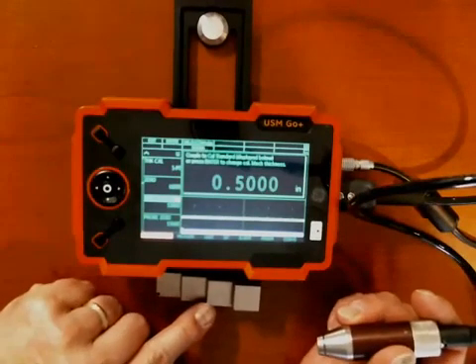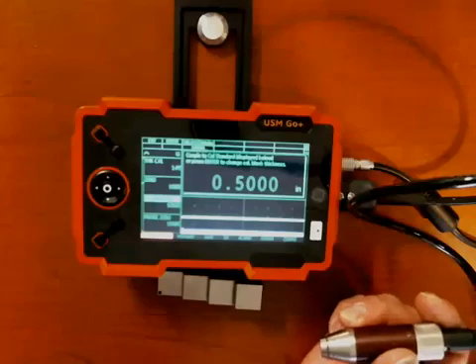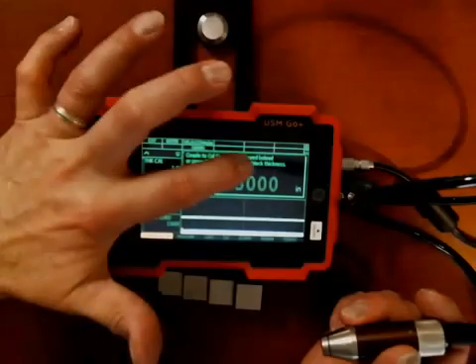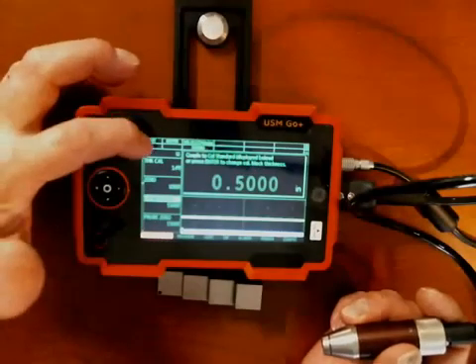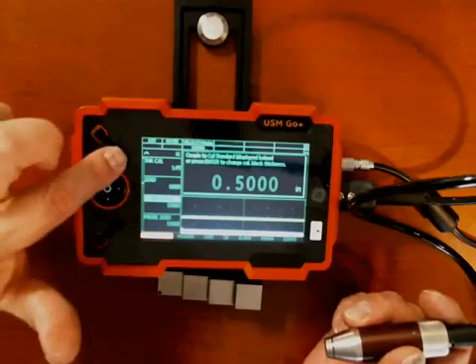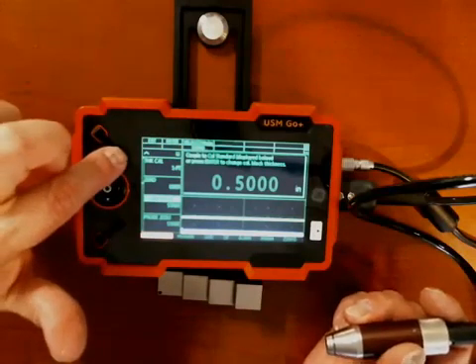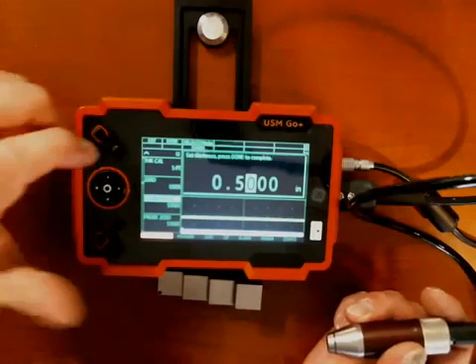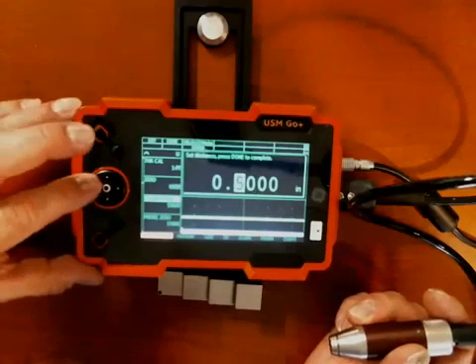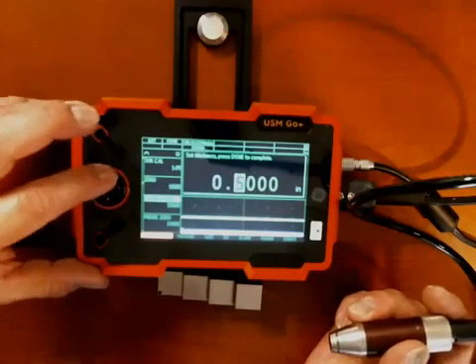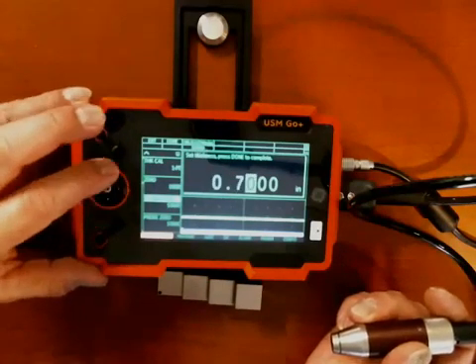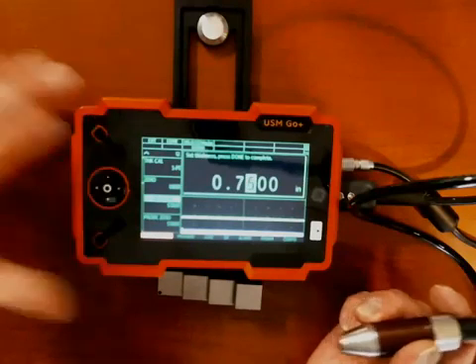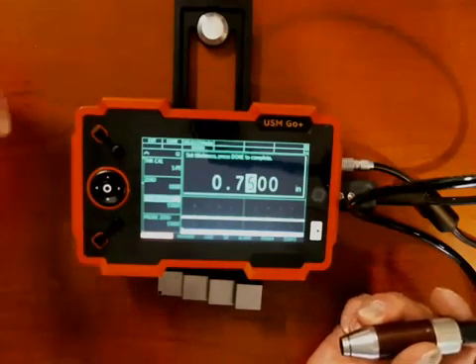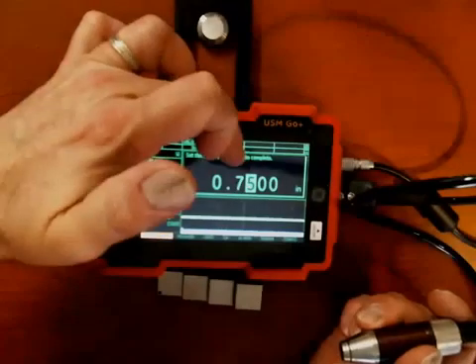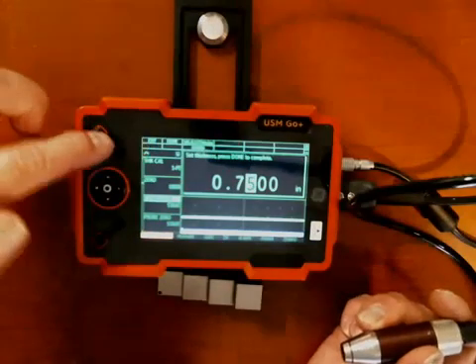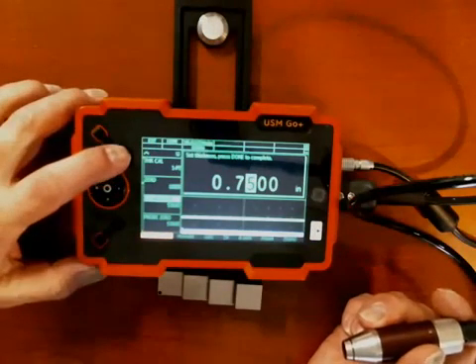Let's say instead I want to go to the 3/4 inch block. All right, the prompt says press enter to change the cal block thickness. Look up here at my function keys. Enter is this key. So I press enter. Now I can go right and left, up and down to change the numbers. And I'm going to tell it I want to calibrate on my 0.75 inch block. Press done to complete. My buttons are exit and done now, so I press done.